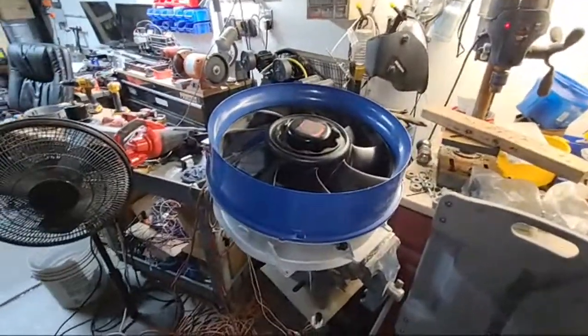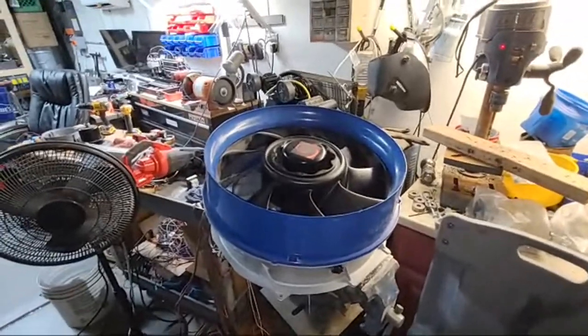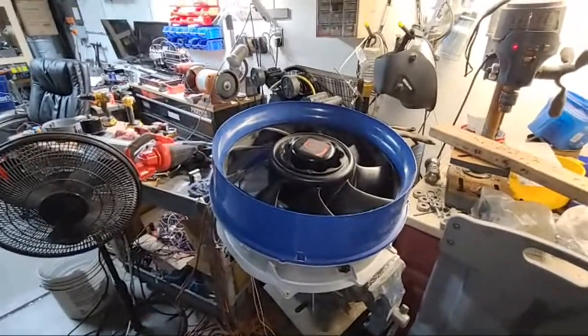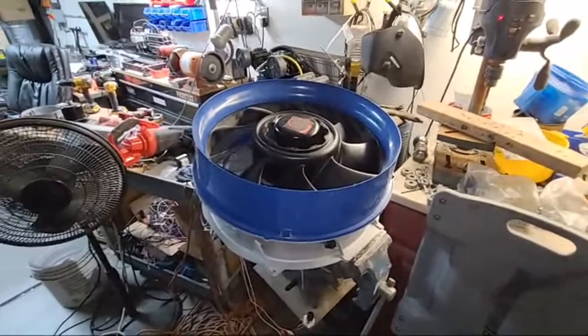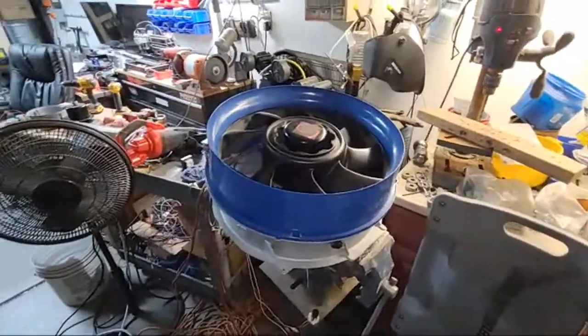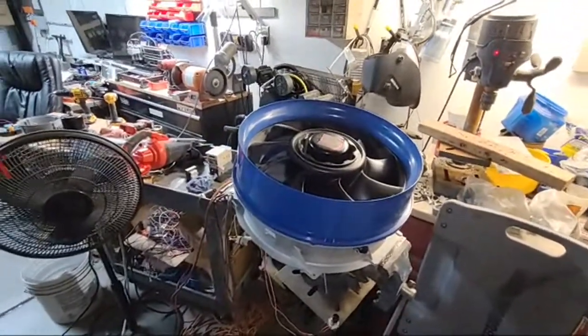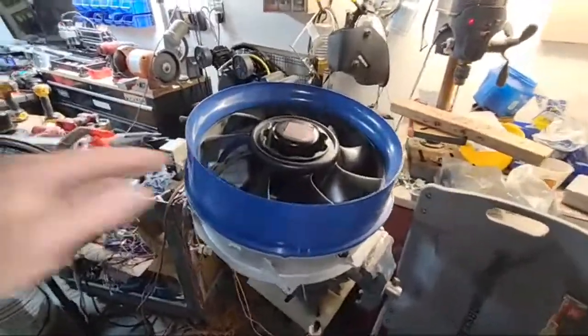That was their wisdom to keep it from tripping high head pressure. I shouldn't say break a belt, but maybe like if your belt was slipping, or a dirty filter or something. But the thing is, you're going back to what the expansion valve was supposed to be doing, which was clamping down, and now it's flooding, so you just can't win.